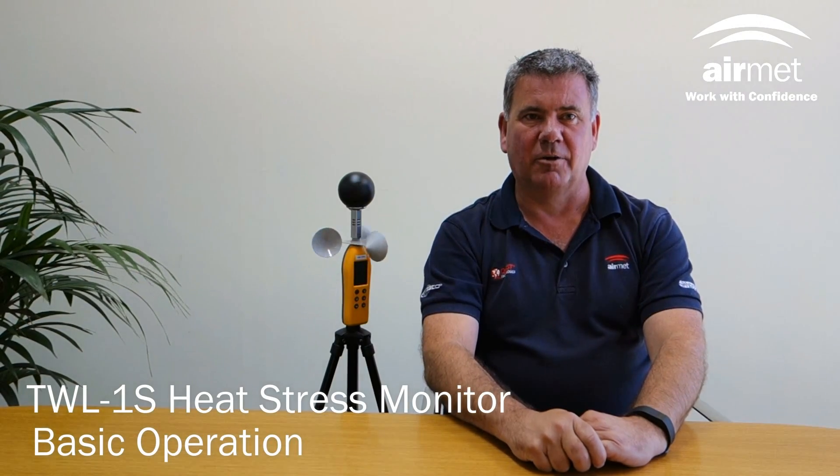Hi, my name is Peter Shields and I'm going to run through the basic operation of the Scarlet Tech TWL1S heat stress monitor. This monitor is designed to measure thermal work limit, or TWL, which is an integrated measure of dry and wet bulb temperatures, wind speed and radiant heat.